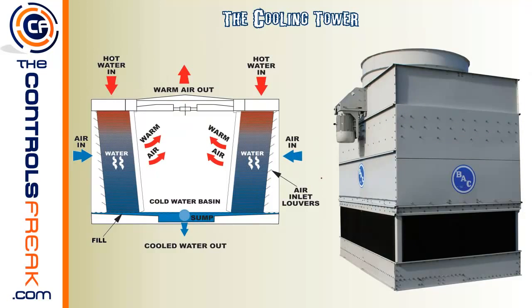A lot of the control strategies for cooling towers come into play when you have multiple towers side by side. You can use staging — cooling tower one, two, three — calling on another tower as it gets warmer. Or they can be dedicated: one tower per chiller. Other strategies include a single tower with multiple fans, such as two fans on a cell.